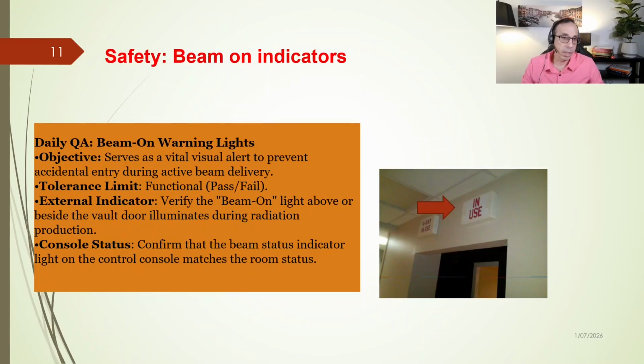Beam on indicators. As you can see in the picture here, just above the maze entrance door, we have beam on indicators. The beam on indicator light is located outside the treatment vault, as you can see here. The lights are designed to give anyone in the vicinity an immediate, unmistakable warning that the Linac is actively producing radiation, preventing accidental entry into the room. Just like our other safety features, this check operates strictly on a pass or fail basis.